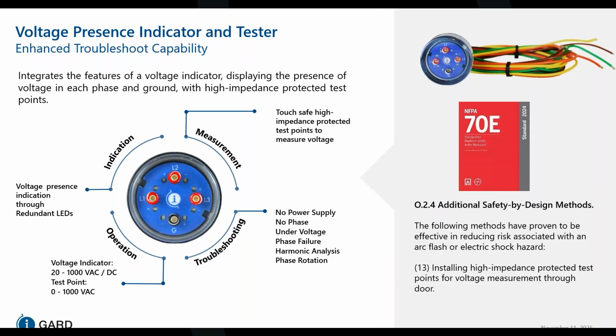The voltage presence indicator and tester is a safety tool that helps you quickly check if electricity is present in a system without direct contact with live wires. It uses bright LED lights to show whether voltage exists in each wire and ground, and it works for both AC and DC power. The device also includes special protected test points that allow safe voltage measurements through the panel door, reducing the risk of electrical shock or arc flash. This makes troubleshooting easier for issues like missing power, low voltages, phase failure, or incorrect phase rotation while following NFPA 70E safety standard.